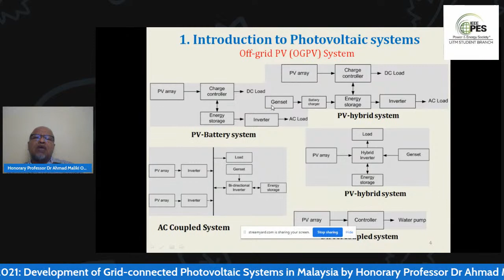The PV hybrid system uses discrete components including a genset. In fact, the AC coupled system also needs a genset in case, especially in Malaysia where December is monsoon season, there isn't enough sunlight to charge the battery. Then we use the genset to provide additional power as an alternative to the PV system. This is usually for large systems, but for a small system we don't need a genset, just PV and battery. This is for powering a community of about 50 households, so we're talking about quite big power.